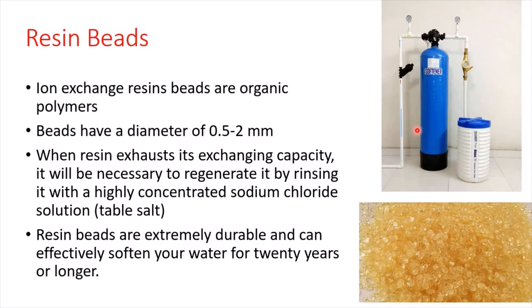Let's have a closer look at the resin beads. These ion exchange resins are organic polymers with a very tiny size — their diameter is between 0.5 and 2 millimeters. The beads are placed in a vessel, and beside this vessel we have a brine tank filled with a sodium chloride solution. Sodium chloride is simple table salt, and we need to rinse the resin beads with this solution from time to time.